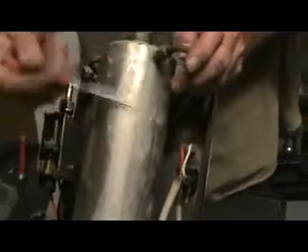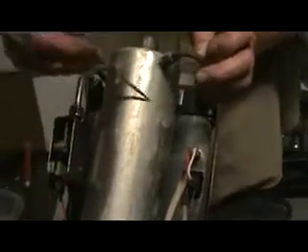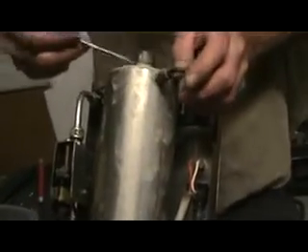That has absolutely no cushion at all. So basically the seals are shot. We know that. But whatever's going on inside of this compartment, you're either leaking water or spitting water through these pinholes.